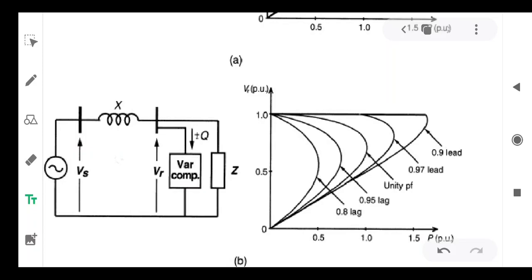The basic philosophy behind voltage stability improvement is that the compensator improves the power factor, and hence the nose curve shifts away from the origin. Therefore, the available margin can be enhanced with the compensator system.